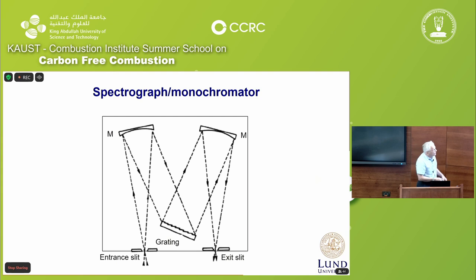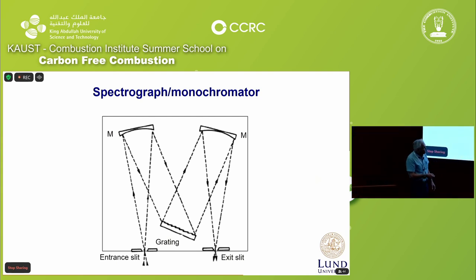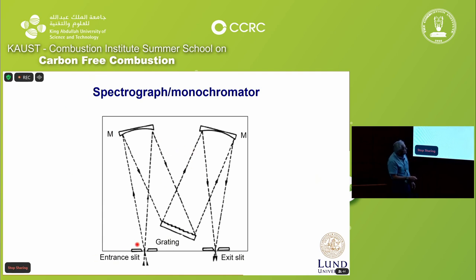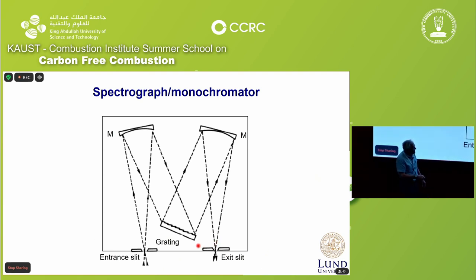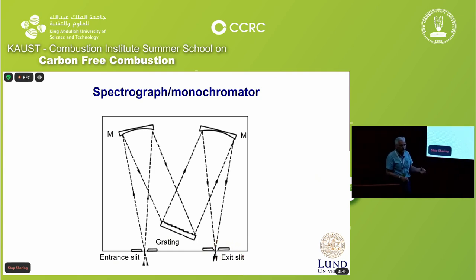To look at different wavelengths, we use a spectrograph or monochromator. You have an entrance slit where light comes from the region of interest. It goes into a mirror, is made parallel, and hits a grating which separates the different wavelengths. Out on the plane of the exit slit you get a spectrum - if you have white light coming in, you get a rainbow spectrum where you can place your detector, which could be a CCD detector or a photomultiplier.